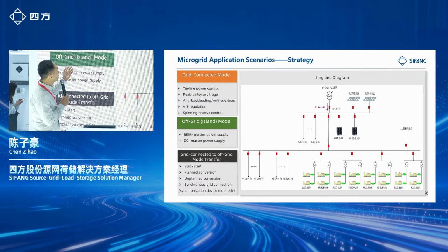And here's some typical strategies for the microgrid application. Basically, we divide it into three parts. The first is the grid connected mode, and second is our off-grid mode, and also the transfer procedure control mode. In the grid connected mode, we focus more on the tie-line power control, peak-valley arbitrage, VF regulation. And for the off-grid mode, we use different units as the main power supply, for example, the BESS and also the DG. And for the mode transfer procedure, we provide this black start capability, planned conversion, unplanned conversion, also our synchronized grid connection.